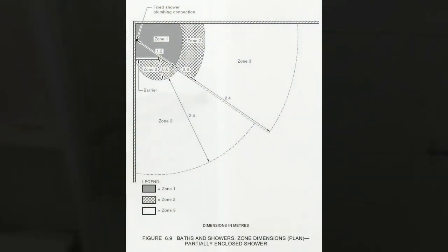Now of course regulations in Australia are different to those in the UK, but I found these two diagrams here which do apply to this situation. This first one shows just a fixed shower outlet with a barrier adjacent to that. It's got their zones marked — zone 1, 2, and 3. And you can see that the switch in this case would definitely be in zone 2, because that side panel, although there's no measurement given, is obviously considerably less than 60cm. It's probably that the whole shower tray is only about that width. So on that diagram, the switch is definitely going to be in zone 2.